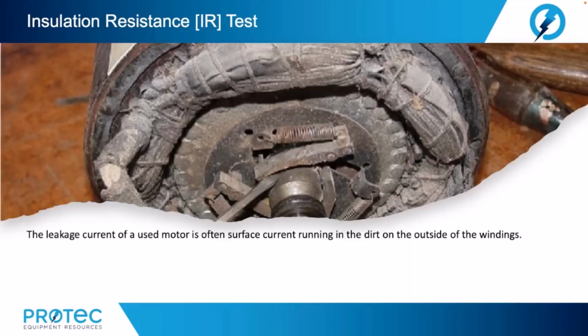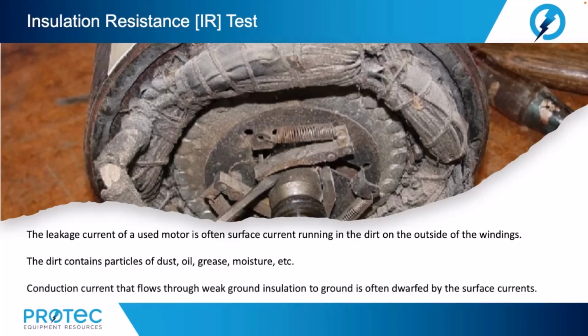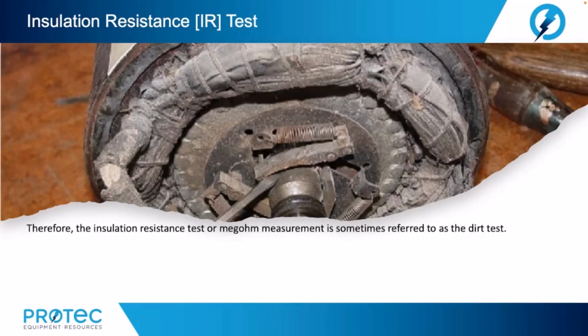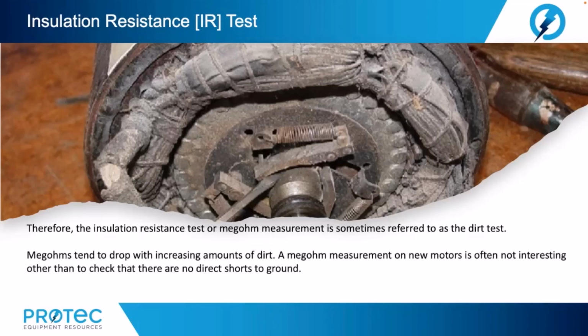The leakage current of a used motor is often surface current running in the dirt on the outside of the windings. The dirt contains particles of dust, oil, grease, moisture, etc. Conduction current that flows through weak ground insulation to ground is often dwarfed by the surface currents. Therefore, the insulation resistance or megohm measurement is sometimes referred to as the dirt test. Megohms tend to drop with increasing amounts of dirt. A megohm measurement on new motors is often not interesting, other than to check that there are no direct shorts to ground. Users will often go directly to a high potential or high pot test, which we're going to discuss later.